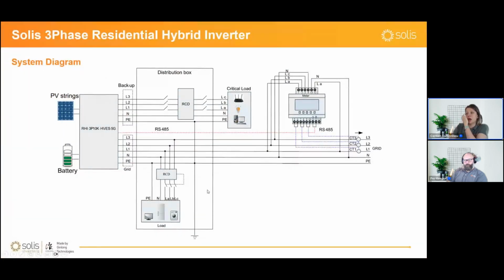And this is how the system diagram for the three-phase actually works. It's the inverter with the PV and with the battery. You have the backup where you would connect the critical loads, and the main grid power supply, the main grid port where you would connect the actual grid. The meter is connected here at the grid connection point and measures export and import, and sends out information through RS-485 to the inverters.